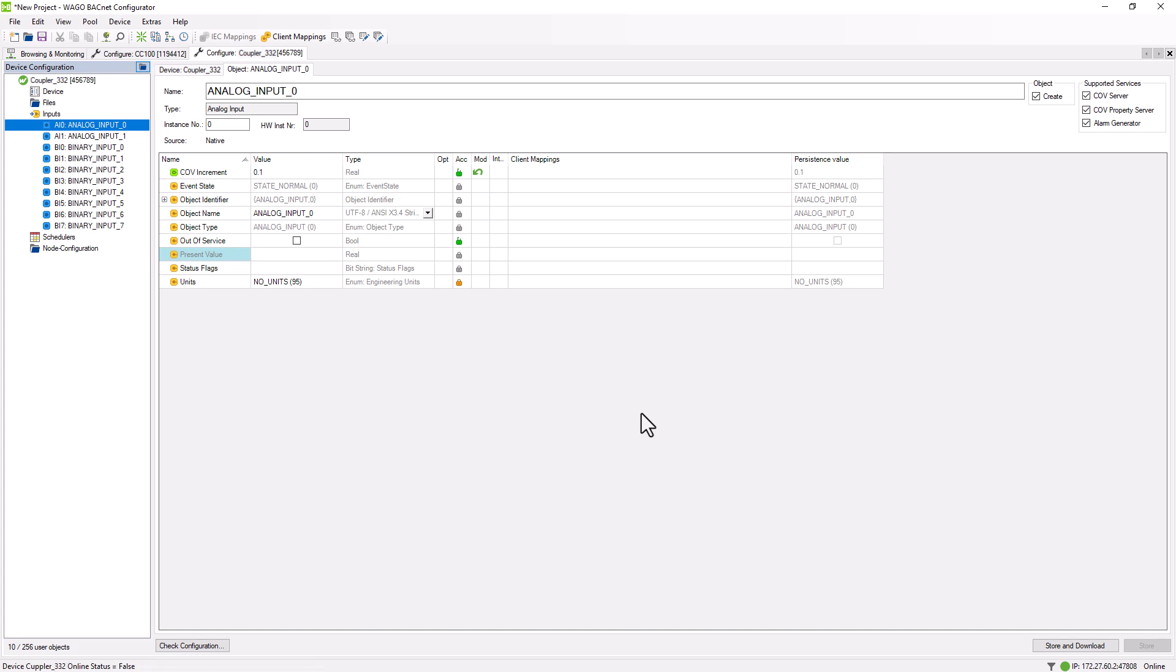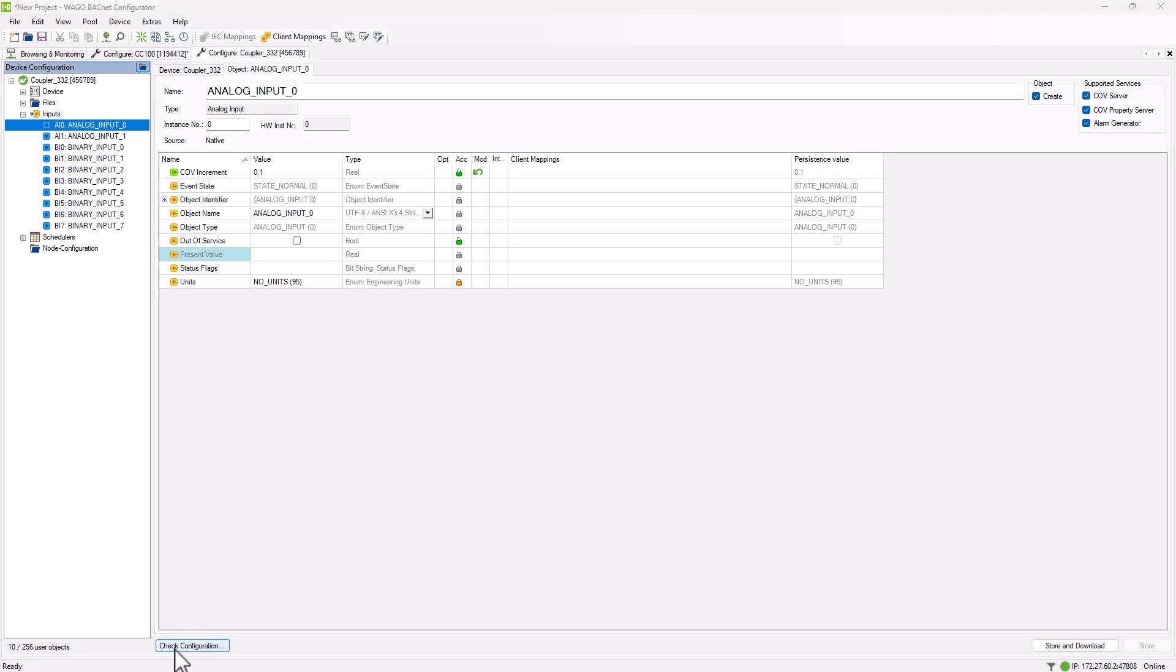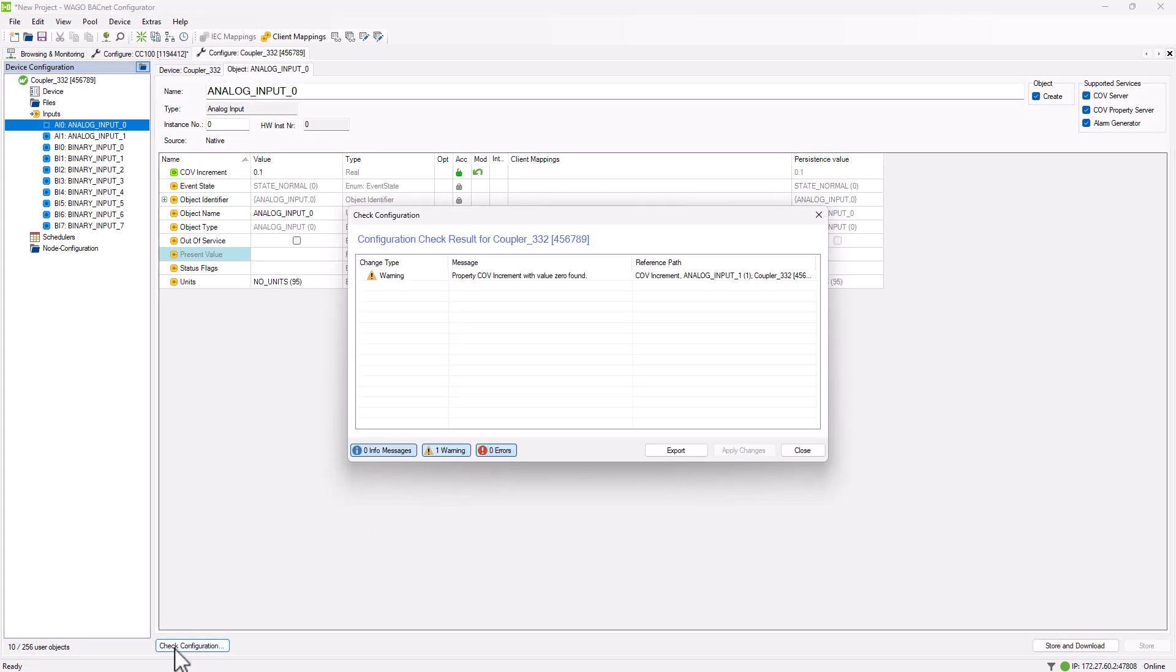Since a COV increment of 0 fundamentally carries the risk of network overload, the COV increment is also evaluated and displayed as a warning during the configuration check. Even if the BACnet project initially runs reliably, unexpected high loads can occur on the BACnet network when expansions or connections to a building management system are made. Therefore, we always recommend entering a technically meaningful value here, even if the value is not initially used.